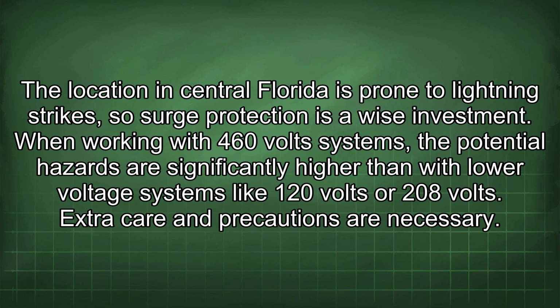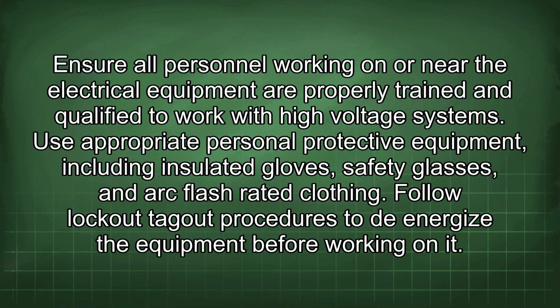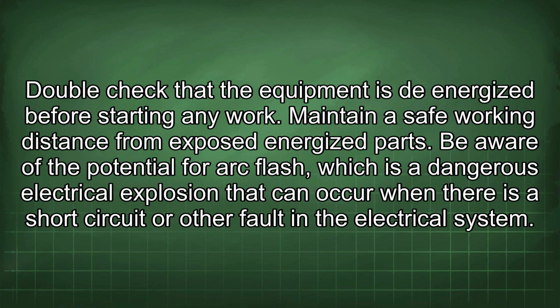When working with 460-volt systems, the potential hazards are significantly higher than with low voltage systems like 120 volts or 208 volts. Extra care and precautions are necessary. Ensure all personnel working on or near the electrical equipment are properly trained and qualified to work with high voltage systems. Use appropriate personal protective equipment, including insulated gloves, safety glasses, and arc flash rated clothing. Follow lockout tagout procedures to de-energize the equipment before working on it. Double check that the equipment is de-energized before starting any work. Maintain a safe working distance from exposed energized parts.